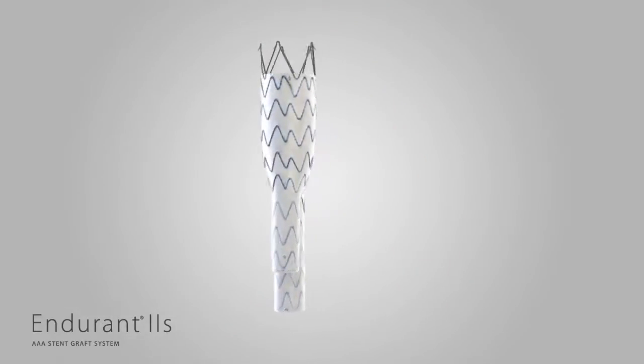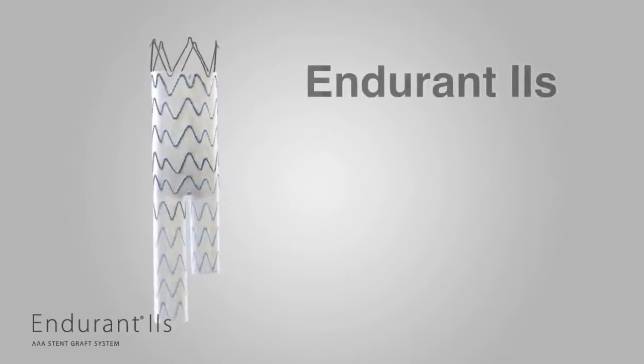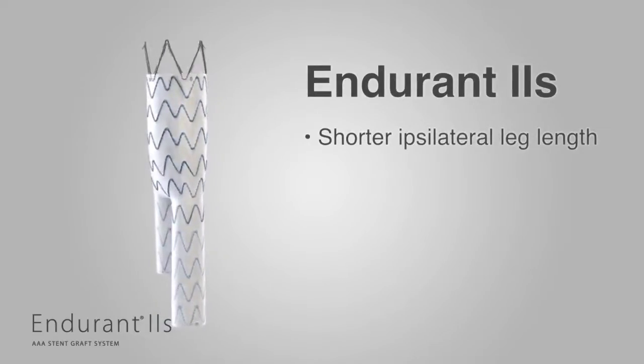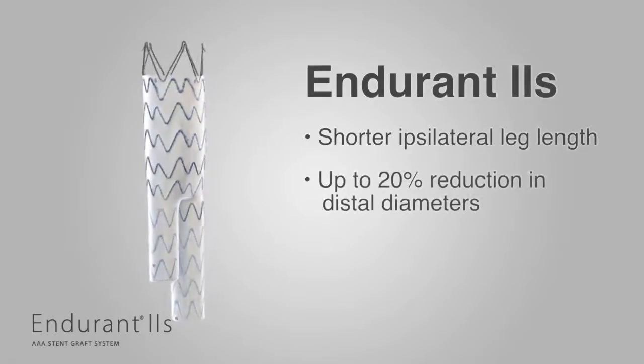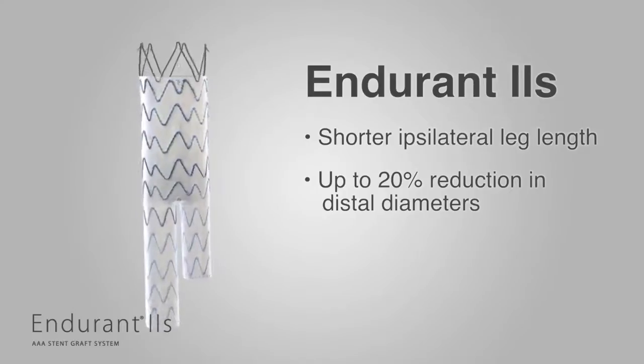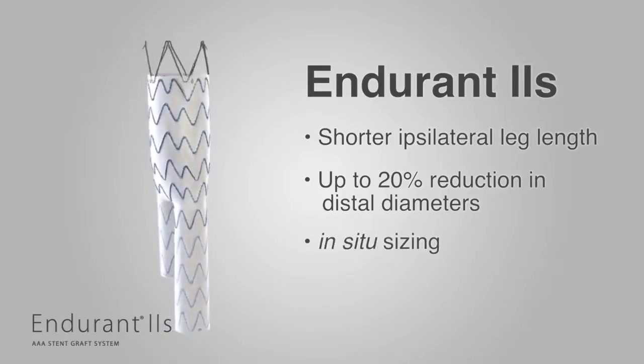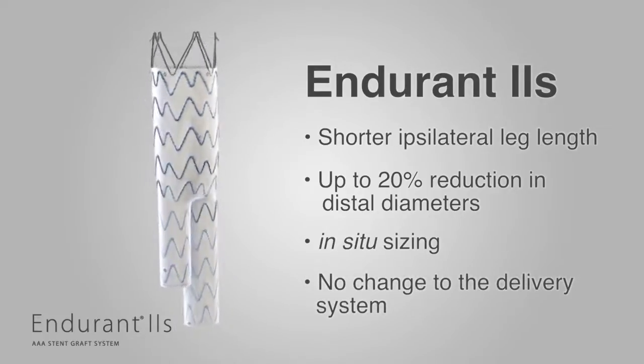Endurant IIs helps improve anatomical customization with the following changes. It offers a shorter ipsilateral leg for more flexible targeted limb placement, provides up to a 20% reduction in distal diameter compared to select Endurant 2 bifurs, and allows for in-situ sizing on the ipsilateral side with select limbs allowing a 3 to 5 stent overlap for adjustment during the case.